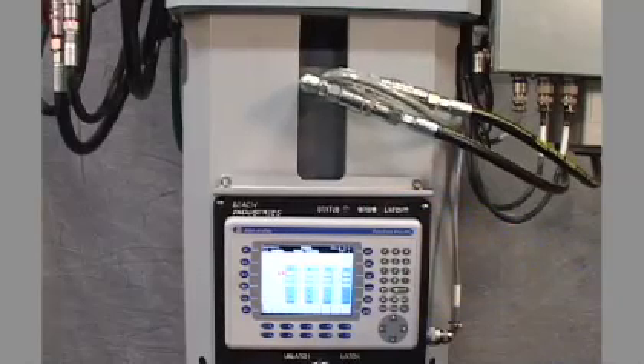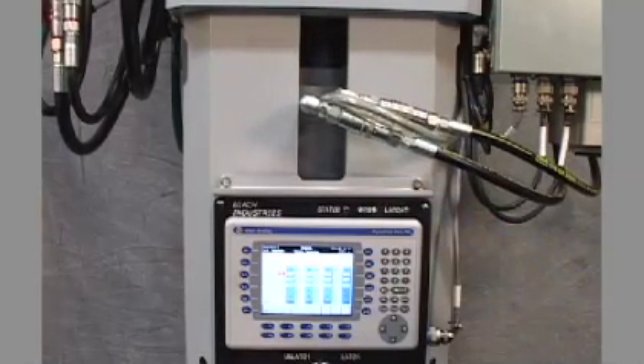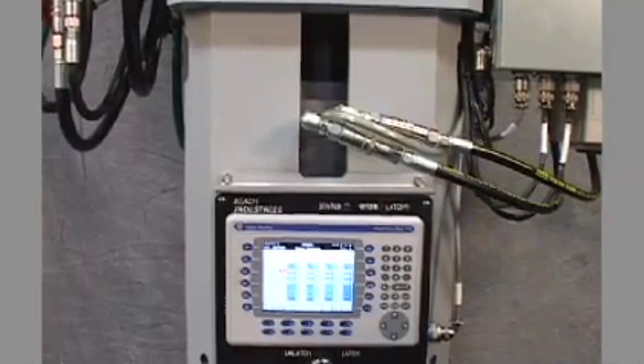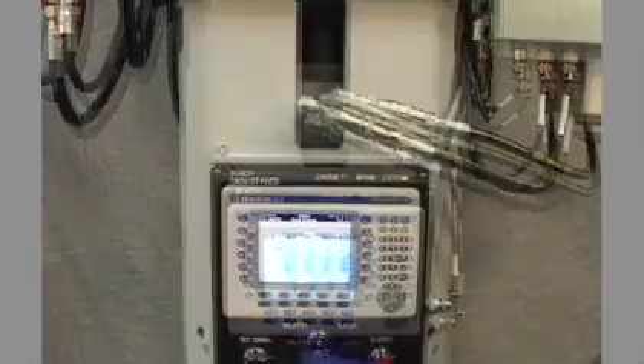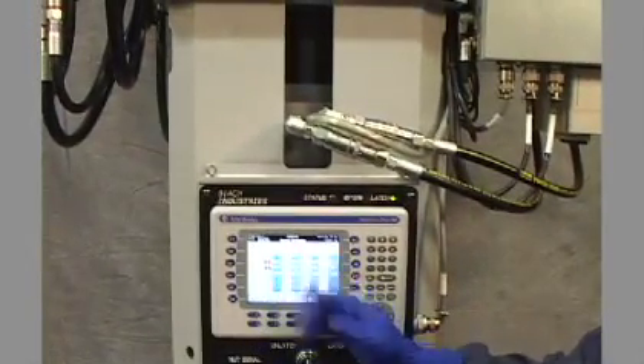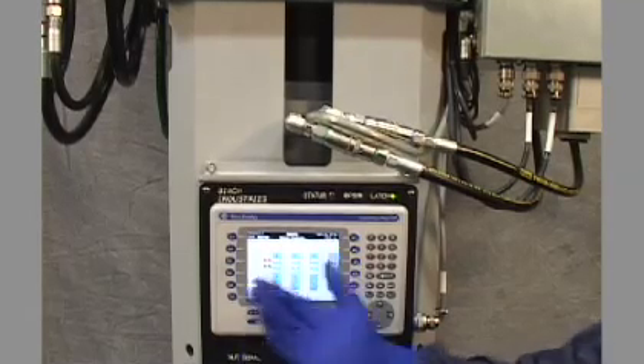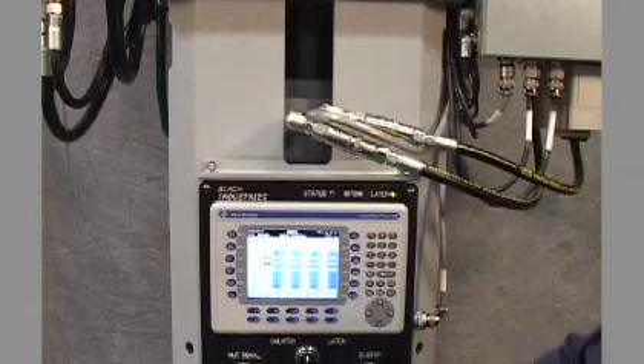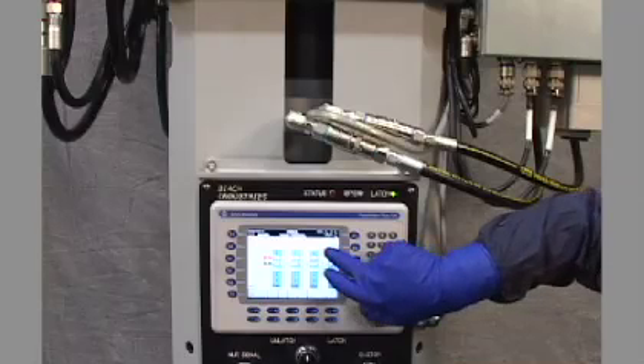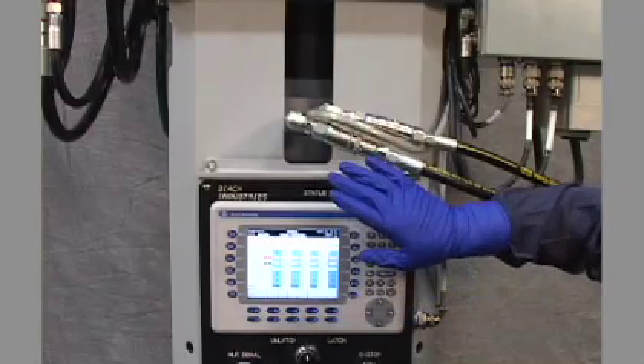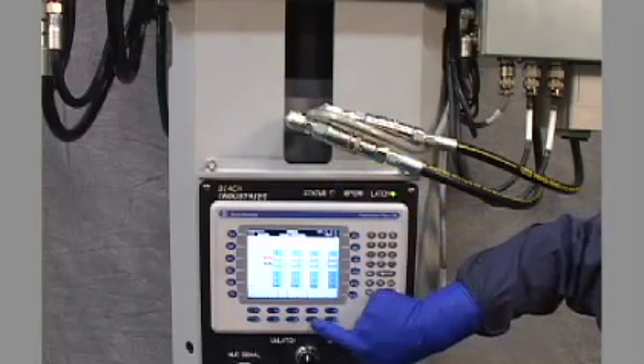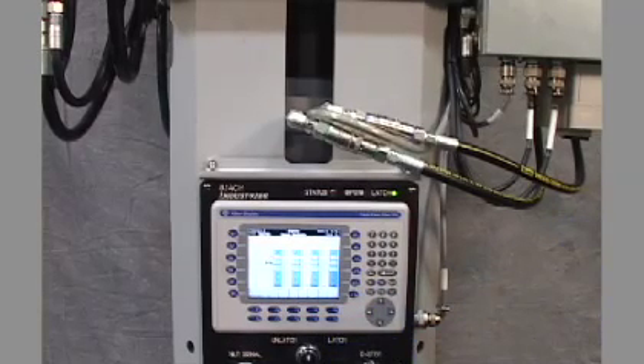The system is now moving down via hydraulic pressure, and it'll latch onto this stud. I get a good puller bar signal. It allows me to go to the next screen. At this point, I can build pressure. So now, my target pressure here is 5,000 PSI. I can go and hit F9 and start to build pressure.